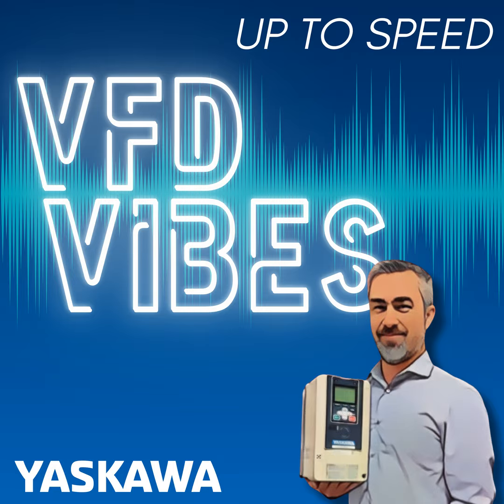Now, we've talked about wye connected systems so far. Is there anything worth touching on in a delta connected system? Yes, delta systems do show up. Power companies are really strange in the fact they really try to save money. And it turns out that theoretically, I can get 3 phase voltages with only 2 transformers, if I hook up the transformers as if I were going to make a delta, and I leave one of them out.